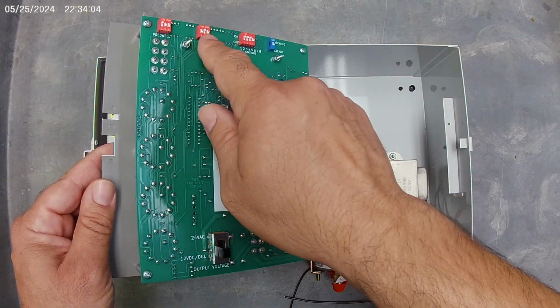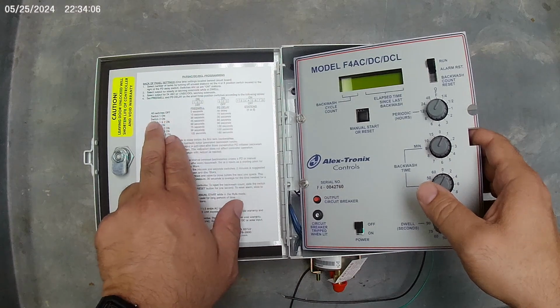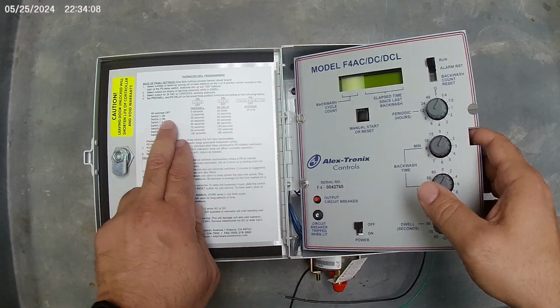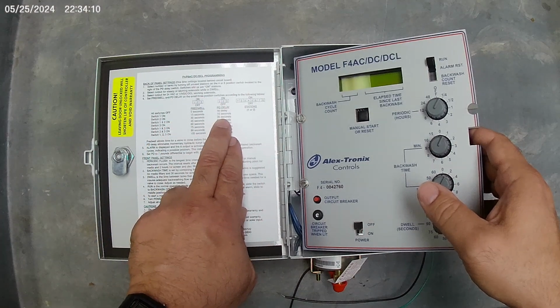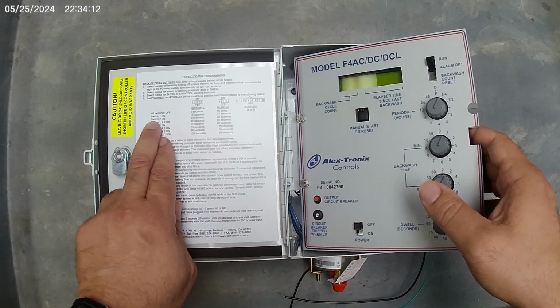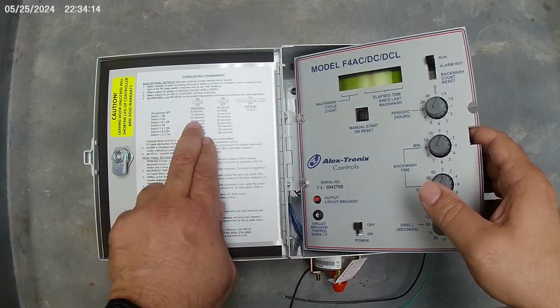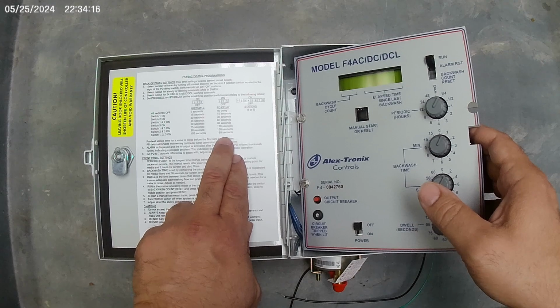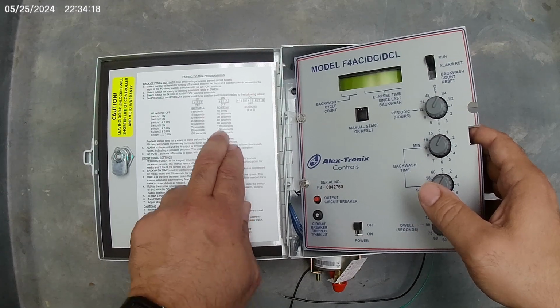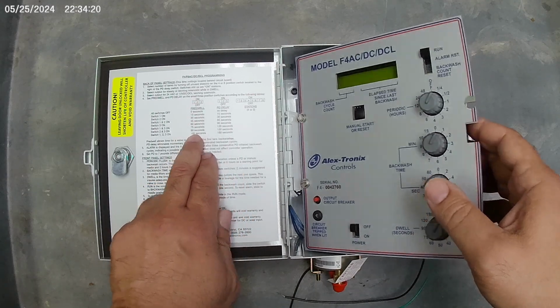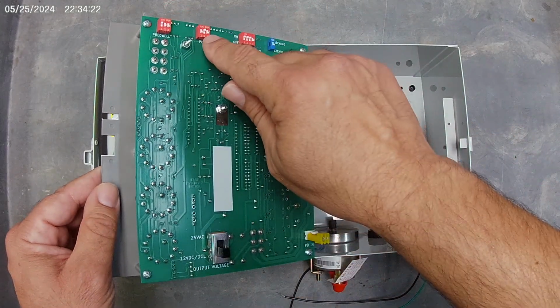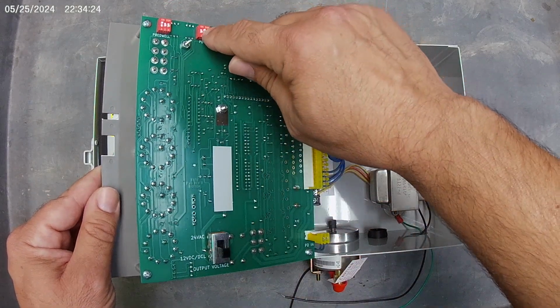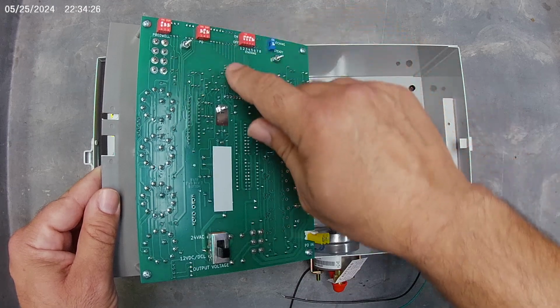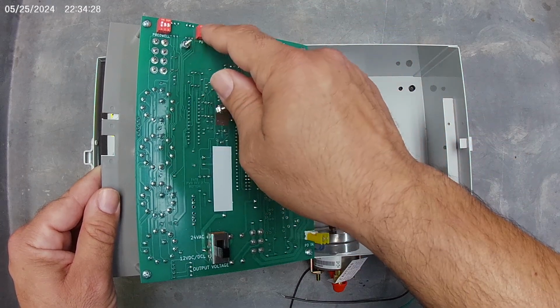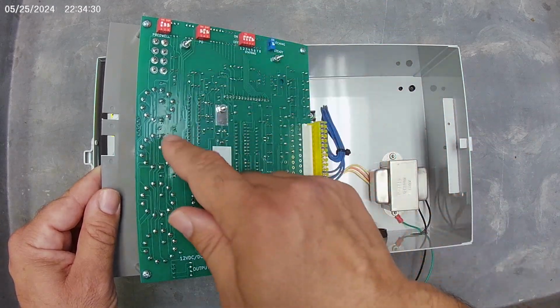Likewise with PD, we follow the same chart. So if we want 30 seconds PD delay, which is a typical value, we would switch 2 on, and they are cumulative all the way up to 180 seconds for PD delay and 105 seconds for pre-dwell. So for example, here we already have our second switch up for 30 seconds. Default setting for most systems is 30.